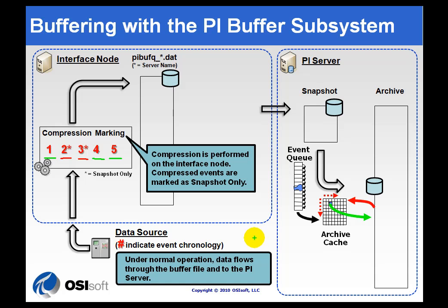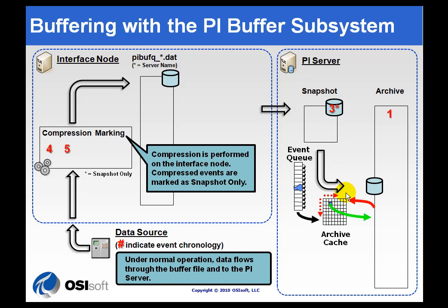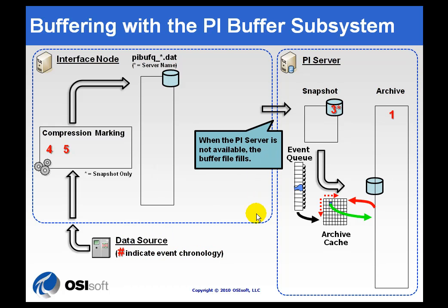We are still sitting on the Interface Node. Normally through buffering, data is placed in the queue, and just as quickly as it gets in there, we send it over to the PI Server. Once it gets to the PI Server, it goes into the snapshot, from there into the Event Queue, and from the Event Queue we send it to the Archive Cache. From the cache, we write it to disk quickly and keep a copy in the cache. That's what happens with data collection with buffering turned on and everything working fine.